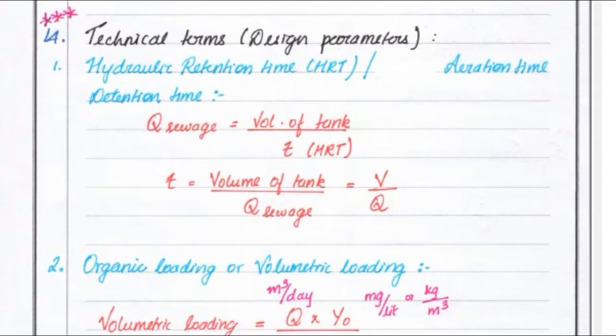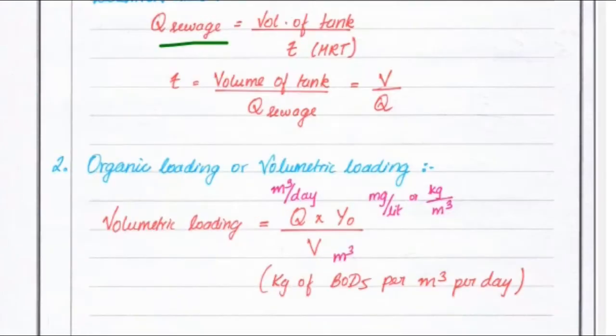First, we have to find out the hydraulic retention time, that is HRT, also called aeration time or retention time. The formula is: Q sewage equal to volume of tank divided by T. So T, that is HRT, is equal to volume of tank divided by quantity of sewage — that is V divided by Q.